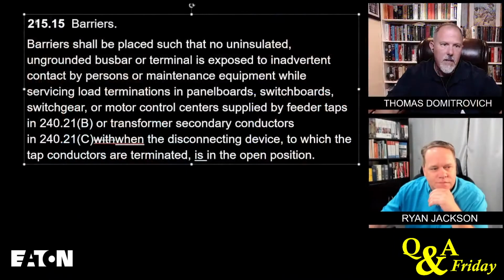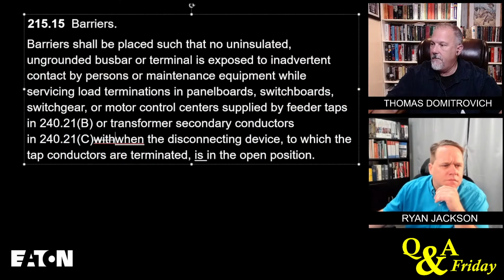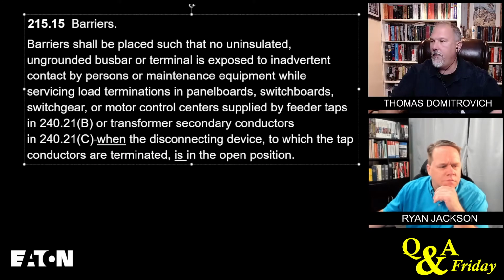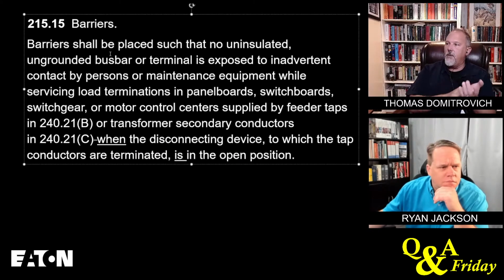Okay, so I'm going to put this language up real quick because this was one of my stimuli for this discussion. 215.15, close this other computer. This is what we ended up with on panel 10. Barriers have to be placed such that no uninsulated, ungrounded bus bar or terminal is exposed to inadvertent contact by persons or maintenance equipment while servicing load terminations in panel boards. So it only impacts panel board, switchboard, switchgear, or motor control centers.